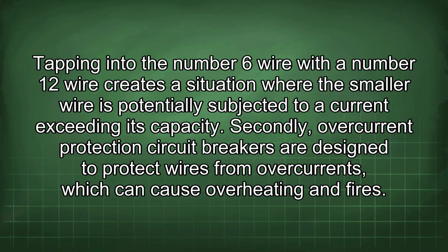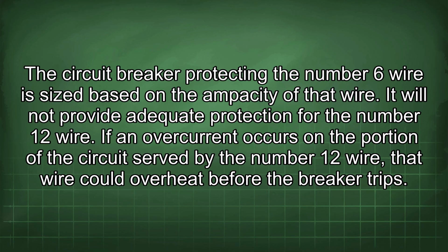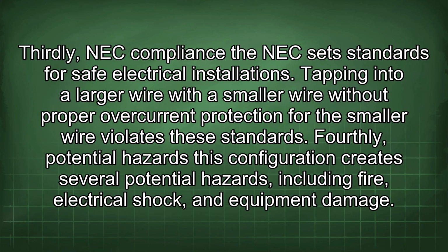Secondly, overcurrent protection. Circuit breakers are designed to protect wires from overcurrents, which can cause overheating and fires. The circuit breaker protecting the number 6 wire is sized based on the ampacity of that wire. It will not provide adequate protection for the number 12 wire. If an overcurrent occurs on the portion of the circuit served by the number 12 wire, that wire could overheat before the breaker trips. Thirdly, NEC compliance.